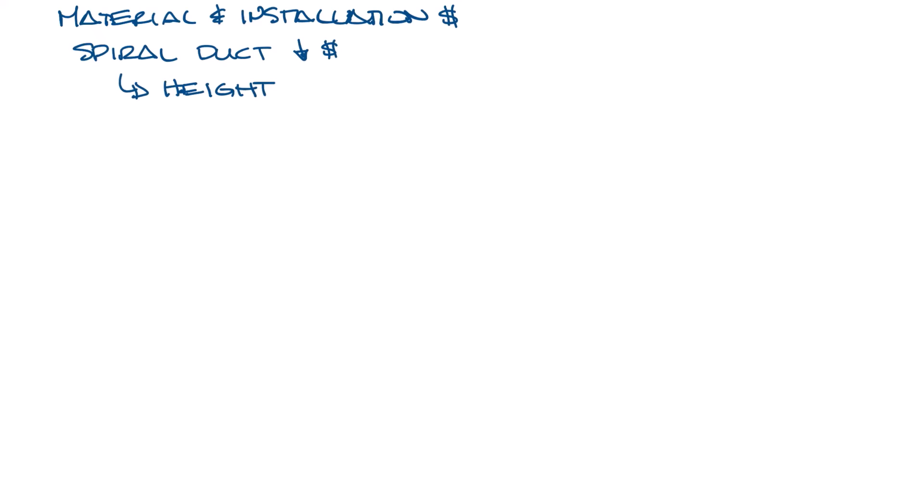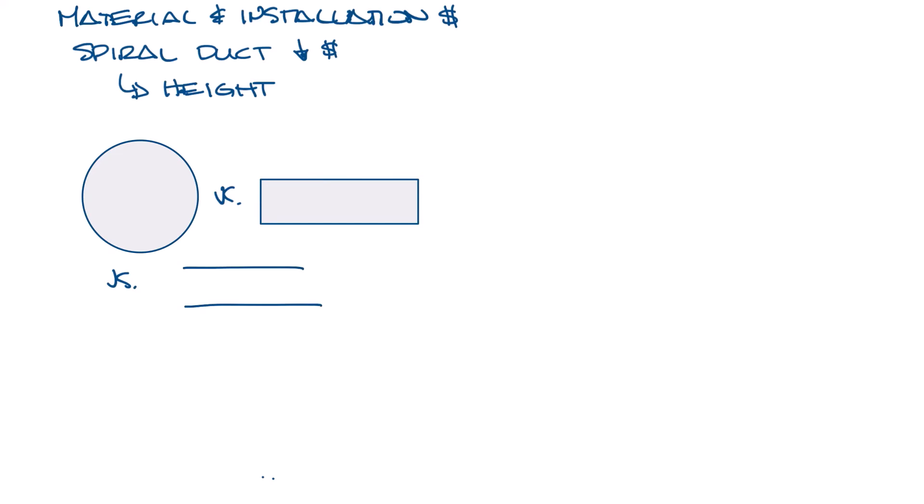Okay, so let's make a little bit of room again. You also have to consider the material and installation costs. Spiral duct may be less expensive and requires less ceiling, so it may be a better option all around in this example. But what if you're comparing 24 inch spiral duct to a rectangular duct? In this case, you may not have the ceiling height to install 24 inch spiral, and a wide but less tall rectangular duct or a flat oval might be your best option.